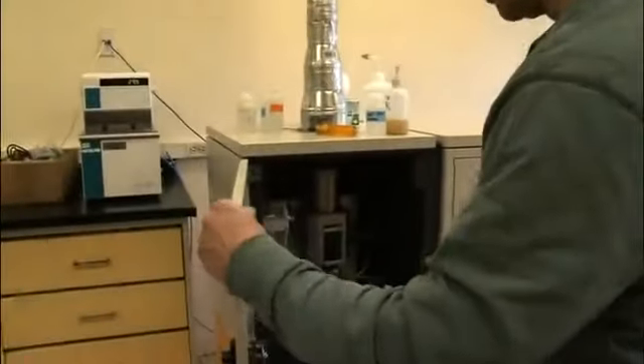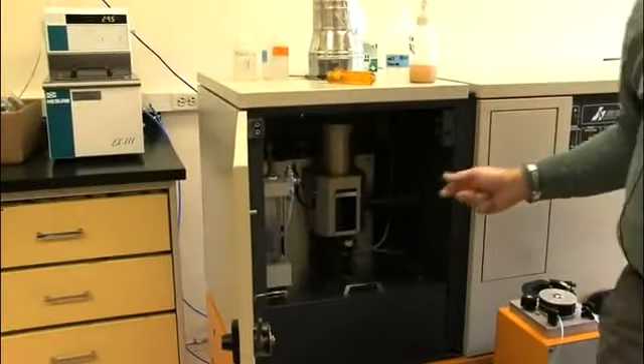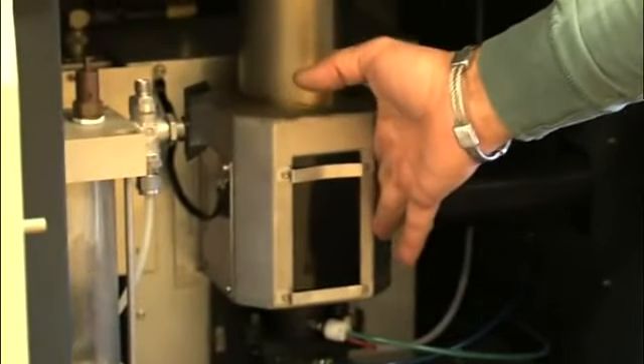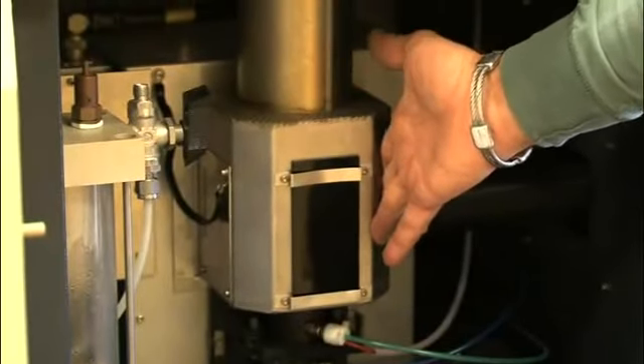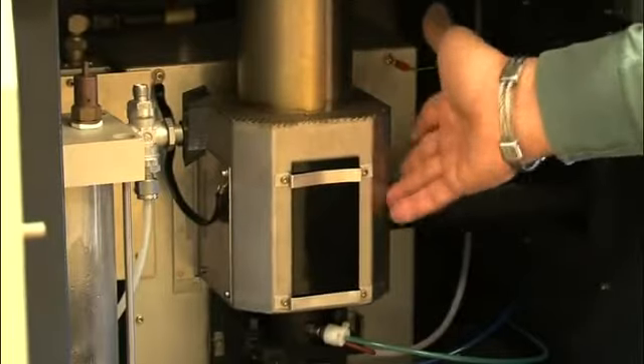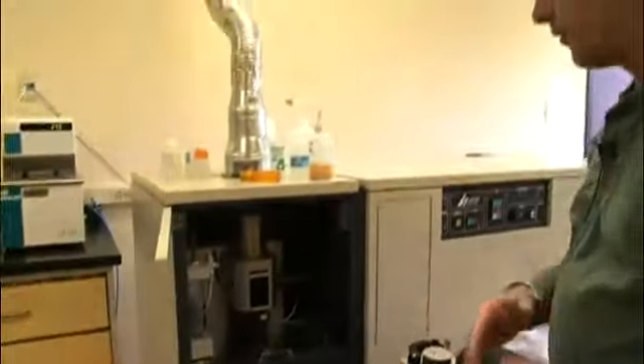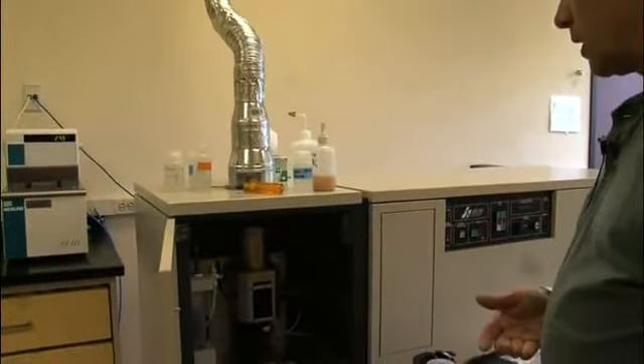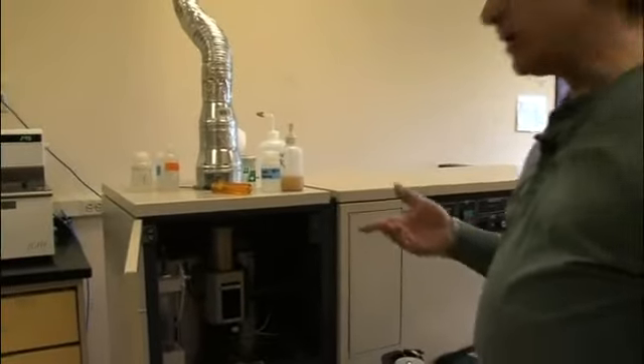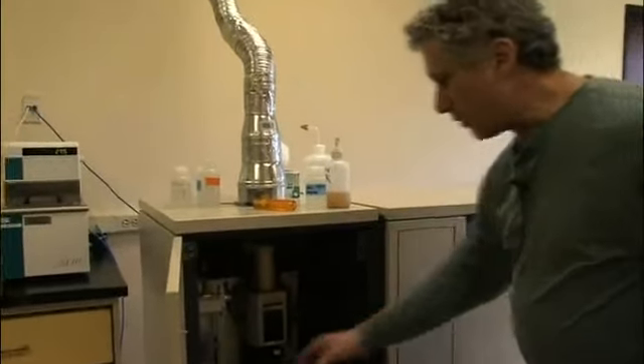One way to know if your exhaust is sufficient: if you can leave your hand on this Faraday cage and it's just warm, then the exhaust is good. If you can't leave your hand on here, it's too hot, then you're not pulling enough out. The system consists of 3 basic areas. You have your sample introduction, which is down here.